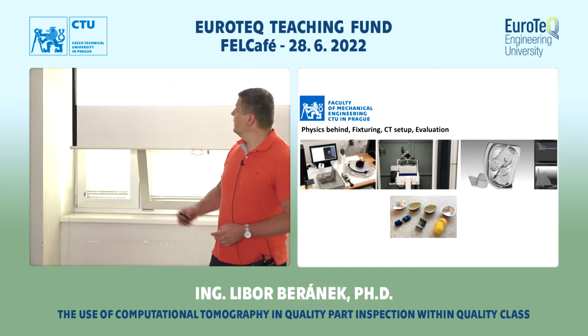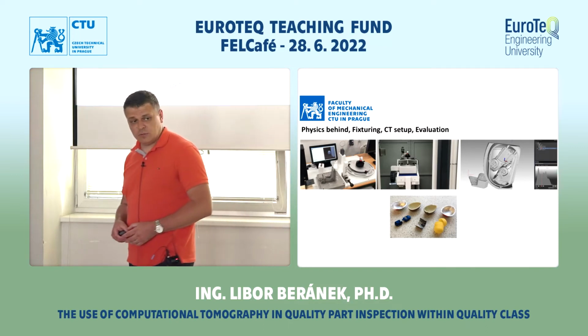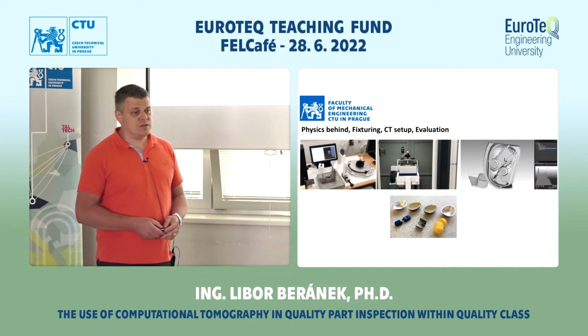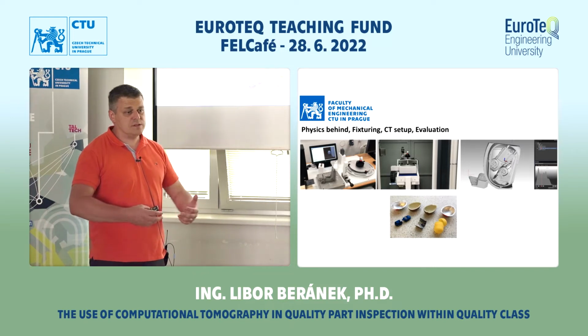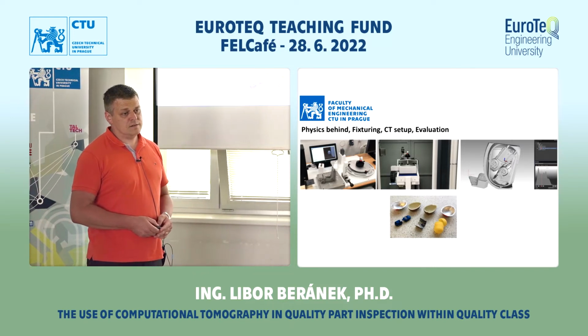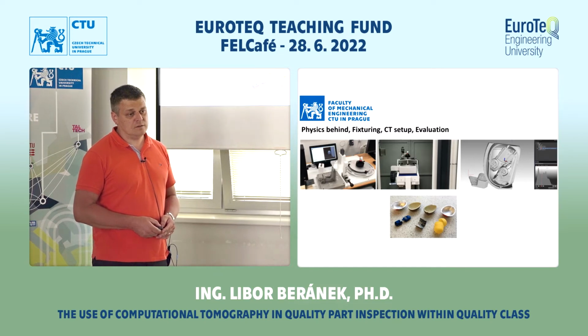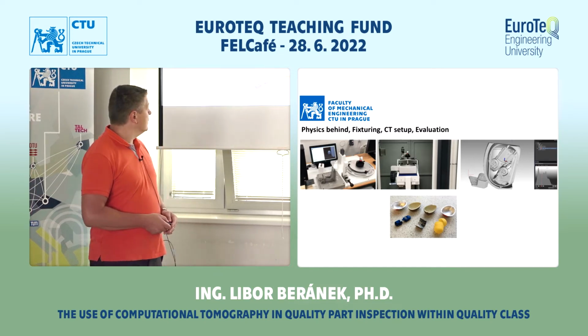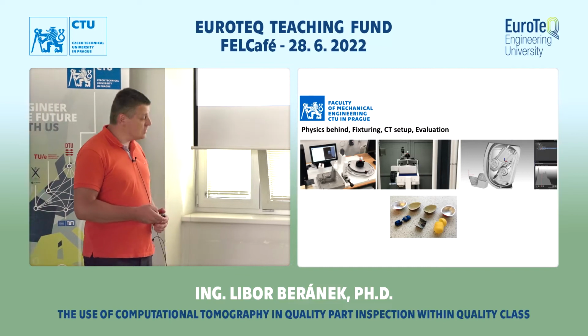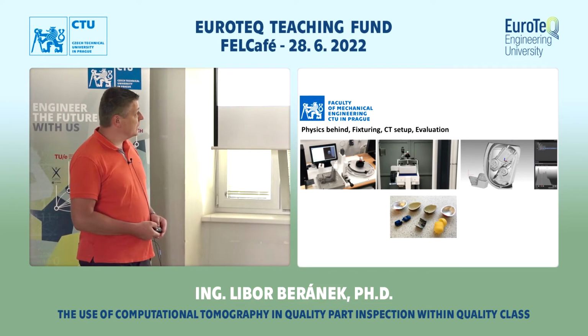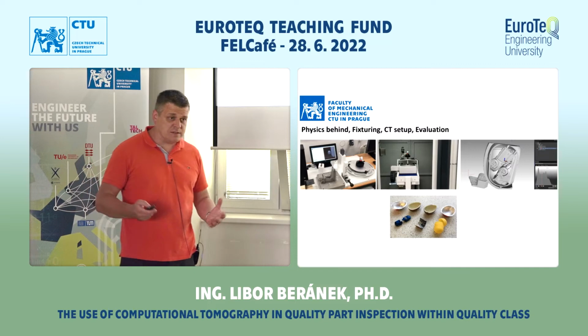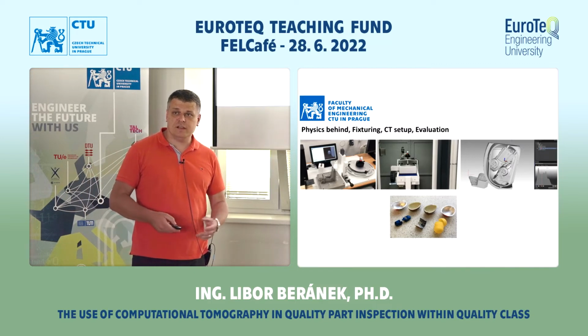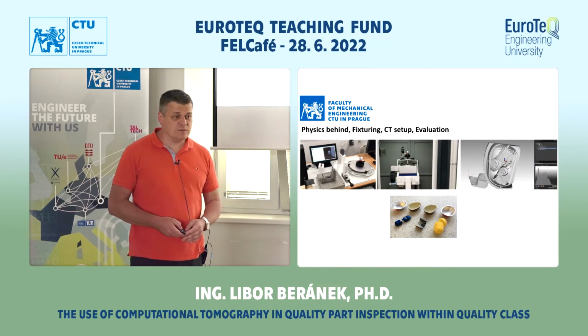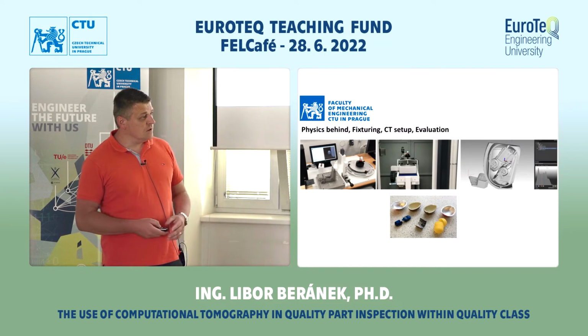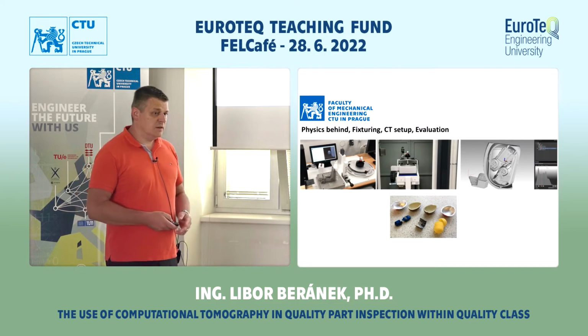So we will explain the physics behind the computer tomography, how the X-ray is generated, how the acquisition of the data is provided on the CT. We will also mention the fixturing, which is quite atypical for these applications, because X-ray basically sees the materials based on their density. So you are also searching for fixtures which are very low density, so they don't affect your imaging, and so on.